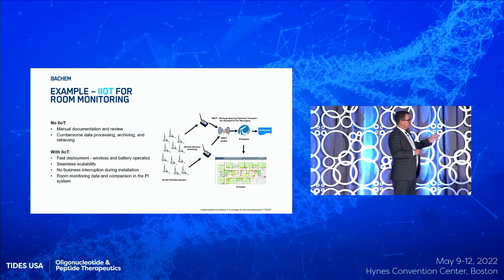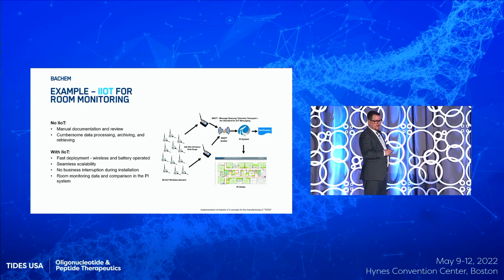For example, these calibrated temperature probes can easily be installed in rooms, and then you have in the PI system a real-time temperature logger. Before that, we had temperature loggers, and someone needs to come in and export the data into Excel, review it, write a report, approve it, and that goes into the archive. Now we just go to the PI system, any room, and go back and check the temperatures for the last 12 months or whatever.